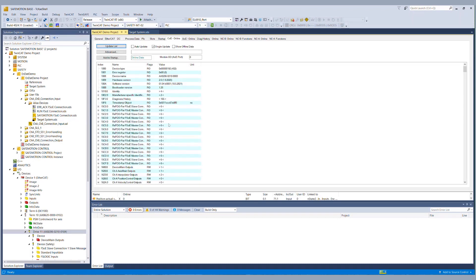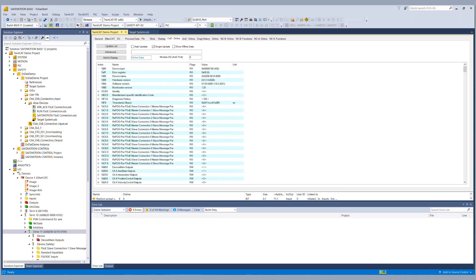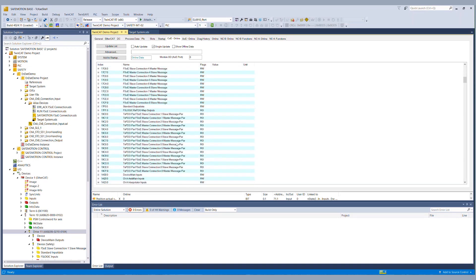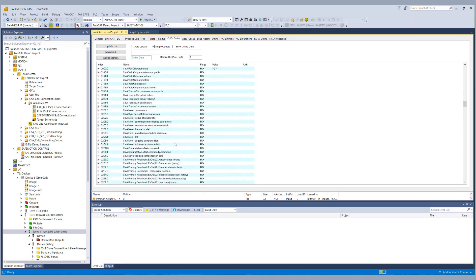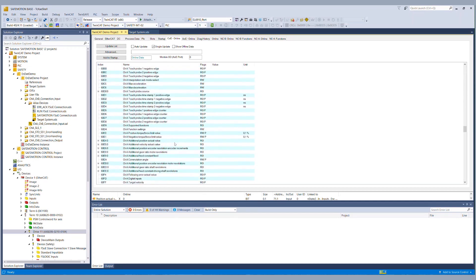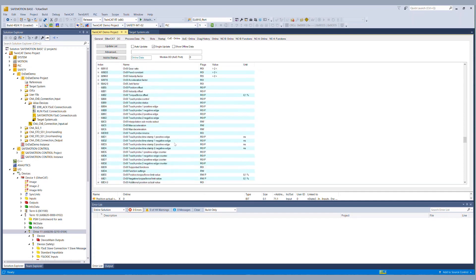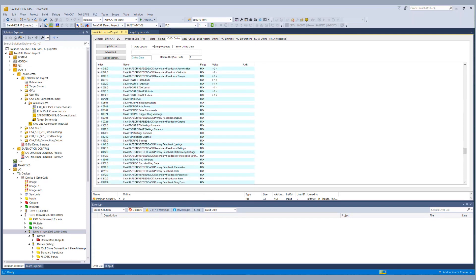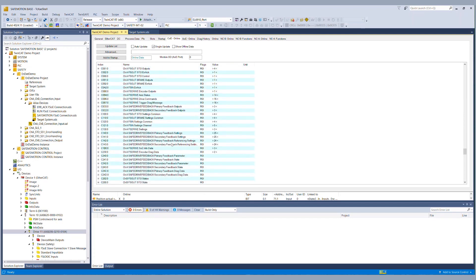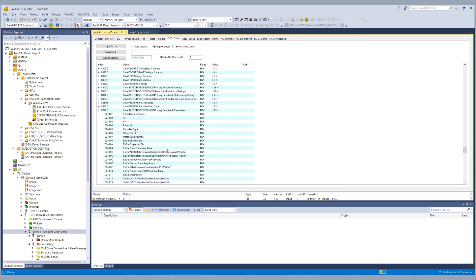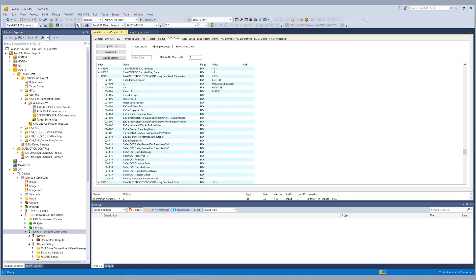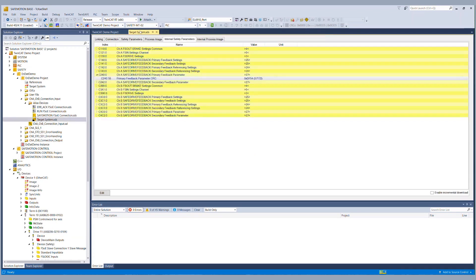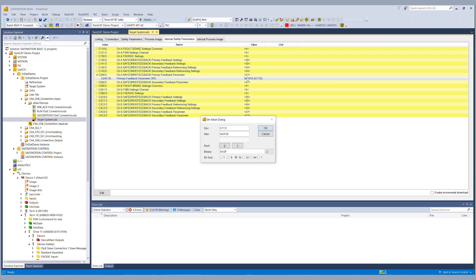So we have to go to the AX8000 COE object, there again we go to the object C240. Under the object C240 we verify all the encoder parameters and the last sub-object is the parameter CRC 06E3 in this case so we remember that CRC and we just have to put it into our safety parameters for the target system.